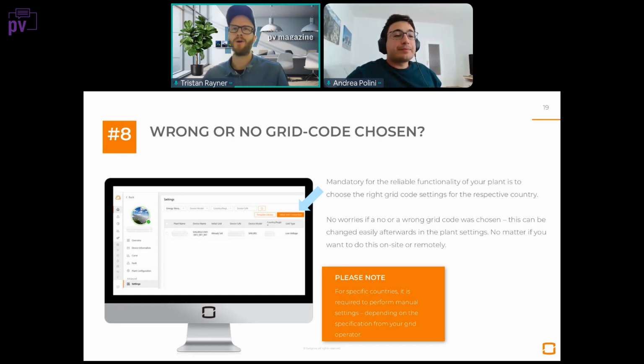So, wrong or no grid code chosen? Yes. We have several cases where, for example, in some countries, you would see issues with the grid, the voltage or frequency of the grid, or the way that the inverter interprets them. For example, error 13 in some countries or error 14 in others. This is most probably related to the grid code that was chosen during the installation.